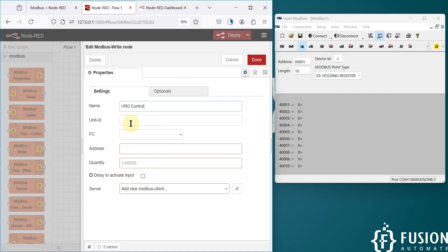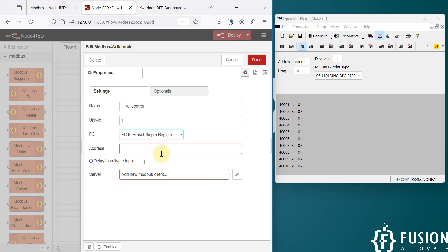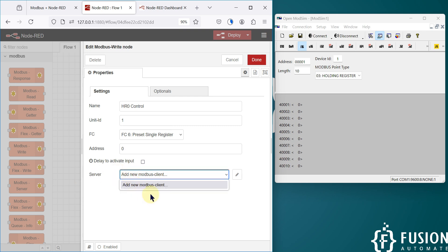For the Modbus write node, I'm going to rename it as HR0 Control. The unit ID is 1. For the function code, since we are going to control only one holding register at a time, I'll select 'Preset Single Register'. Here we provide the address of the register we want to control — we are controlling the very first holding register with address 0.